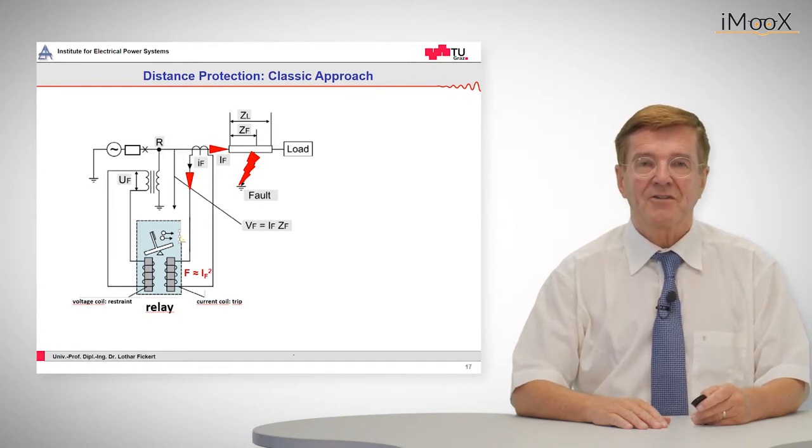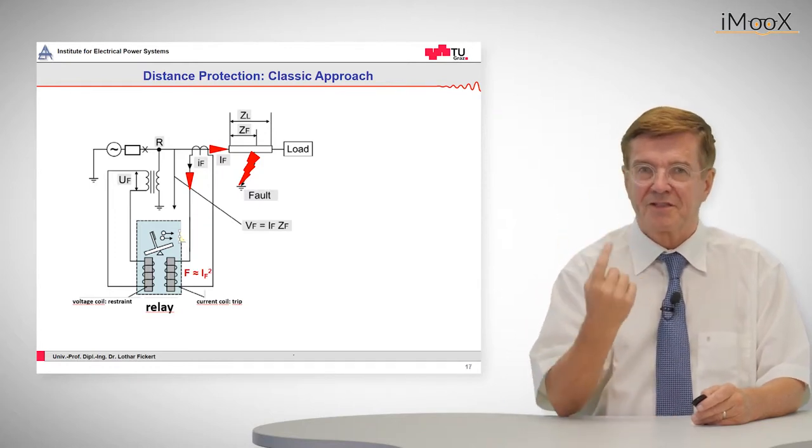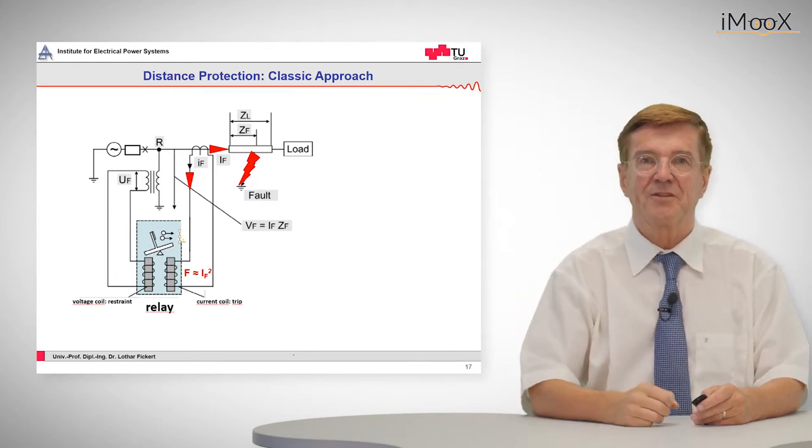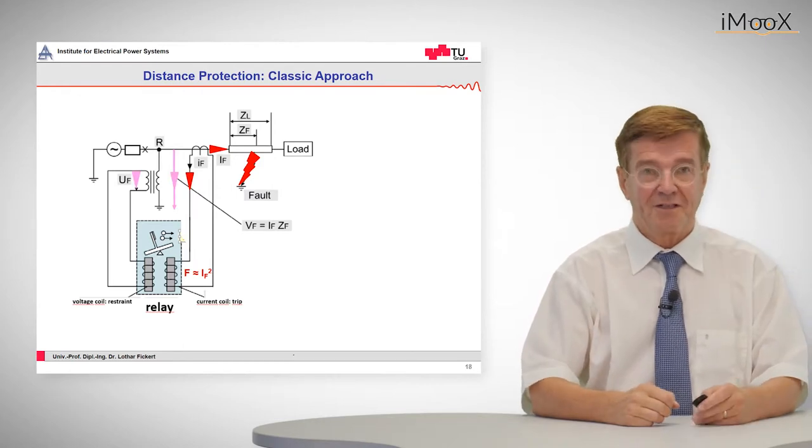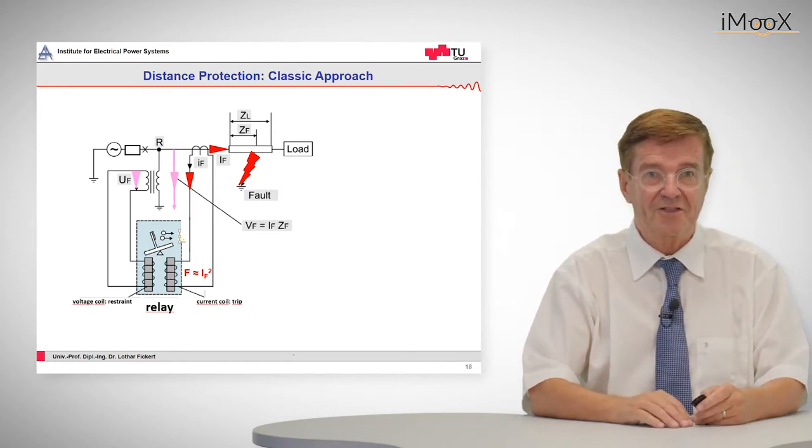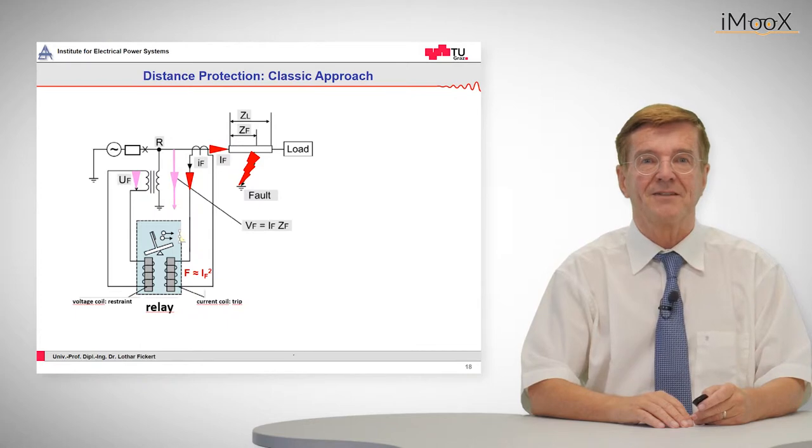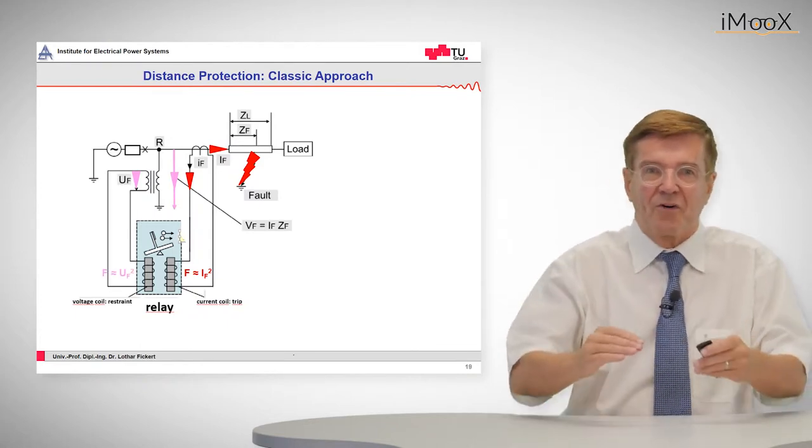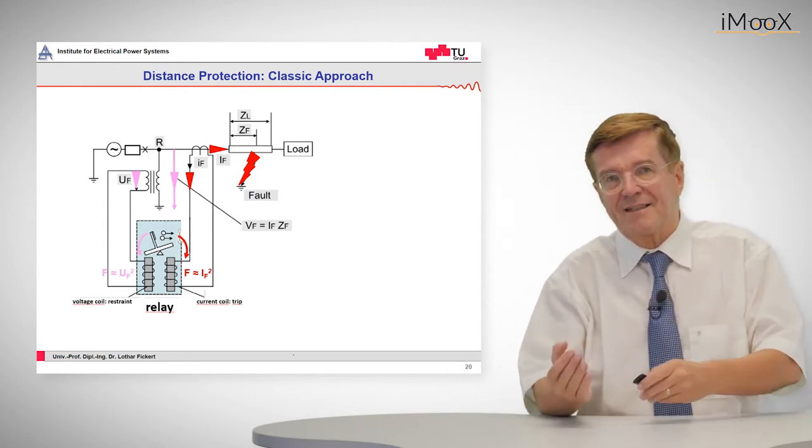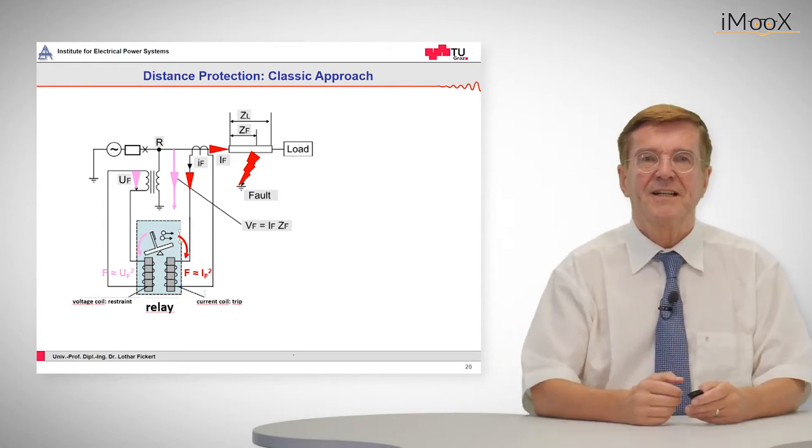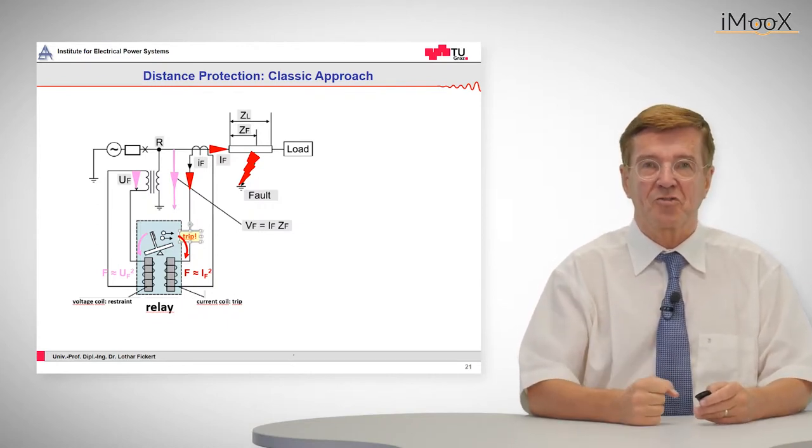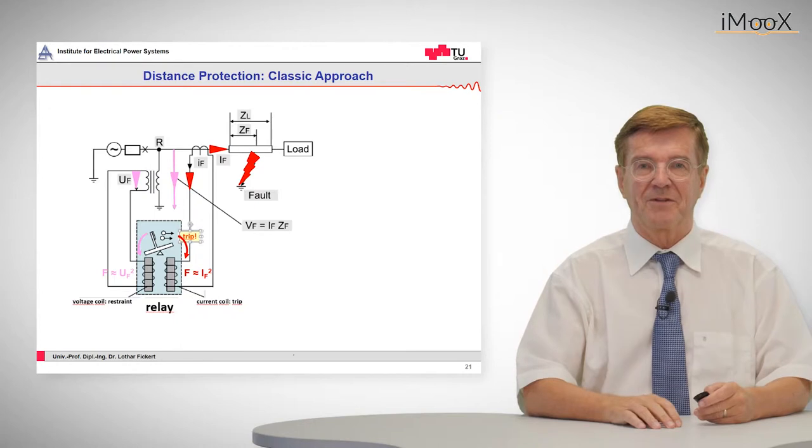So at the current coil we have a current flowing through this coil and it magnetizes and tries to pull this lever down to its side. On the other hand we have a voltage, a residual voltage, which magnetizes the restrained coil, the voltage coil, and these two forces act either to the right or to the left side. And if we have one point where they are equal the trip force is strong and we activate a trip.